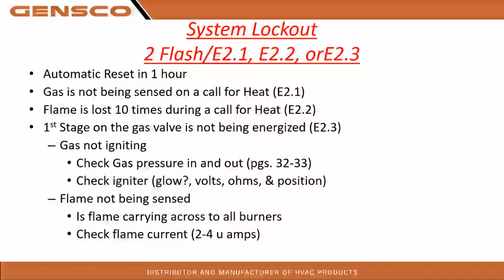So obviously, when we have a first stage error not being energized, we're going to look, right? Why isn't the gas igniting? Do we have the right pressure in and out? The maximum pressure inlet you can have on any of our gas valves is no more than 14. So in an LP situation, we can see where we can have pretty high inlet pressure, which could hold off our gas valve from doing what it needs to do. So we're going to look at gas pressure, what's coming in, what's going out. We're going to check the igniter, make sure it glows. What's the ohms? What's the position of it? Is it in the hot spot on the burner? And what kind of igniter is it? Is it 80, 120 volts, and so on?